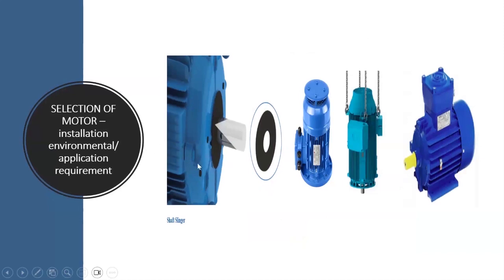For instance, we can see on the screen a motor with a shaft slinger and a motor with a rain hood and a motor with eye bolts, and we have an explosion proof motor. So if the motor is going to be mounted vertically, you have to specify that you need a motor with a shaft slinger. But the general purpose motors, they come without a shaft slinger. So without a shaft slinger, with continuous exposure to rain, to slurry, to dust, they will permeate through the seals of the motor and the bearings will be lost in no time.